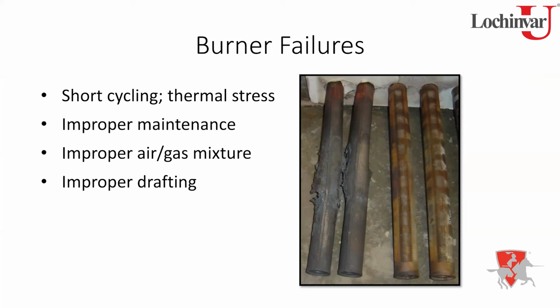It's going to float up and down, which will eventually create stress fractures across the surface of the burner if it's done too frequently. Eventually, those stress fractures will get bigger and bigger, and then you'll basically just fail the burner completely at that point.